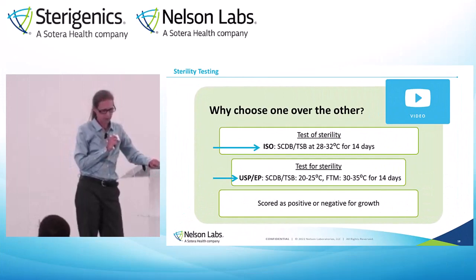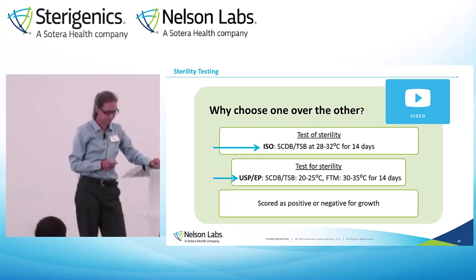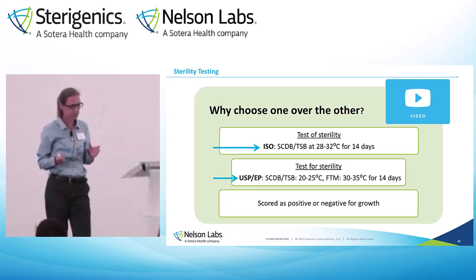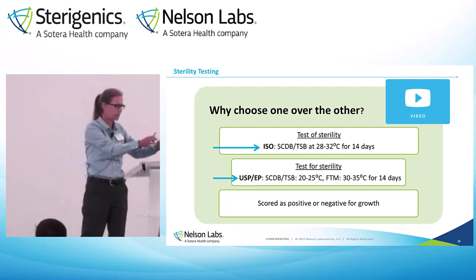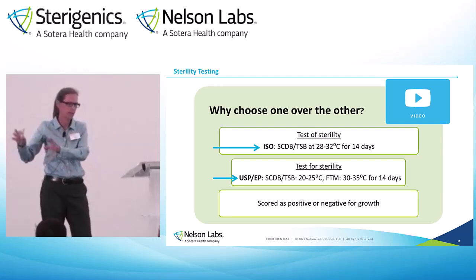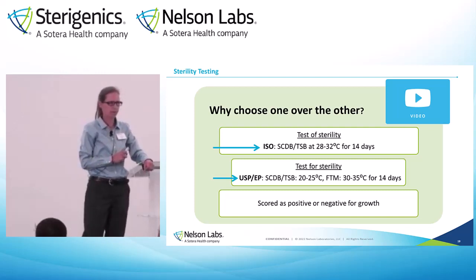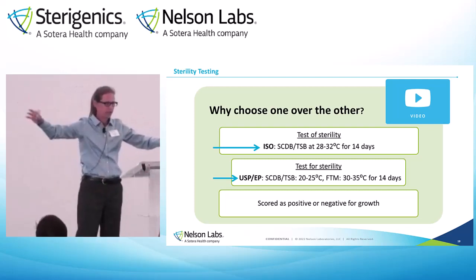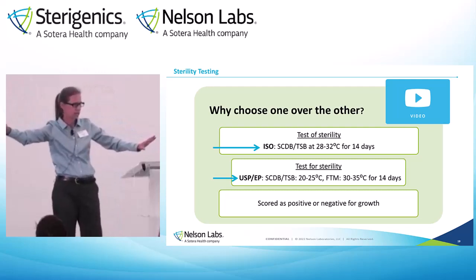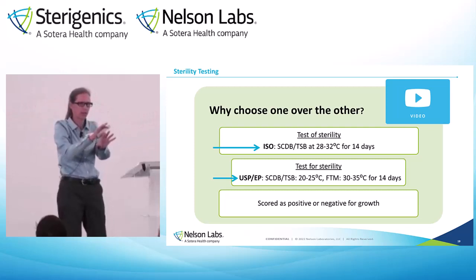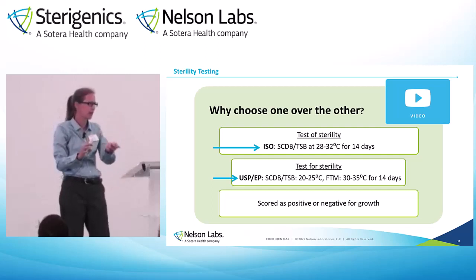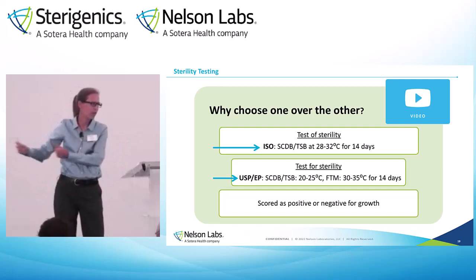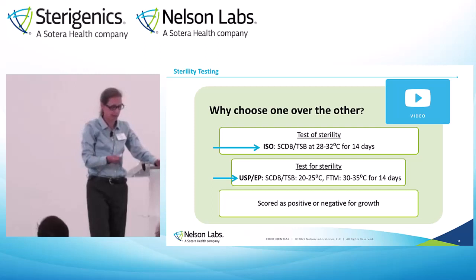Sterility testing — sometimes called a test of sterility, sometimes called a test for sterility. The ISO test, or test of sterility, is for terminally sterilized product. So you make the product, send it to the irradiator or the EO facility, it gets sterilized, and you follow the ISO method. The USP method is for aseptic processing — where you sterilize the container and the drug product or fill separately, then put those two together as cleanly as possible under conditions where you really hope no organisms get in.